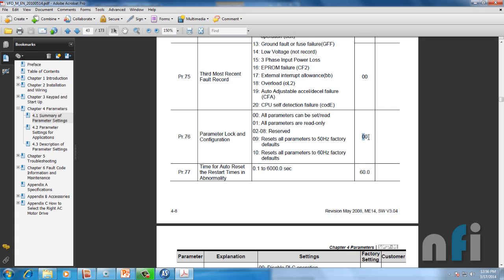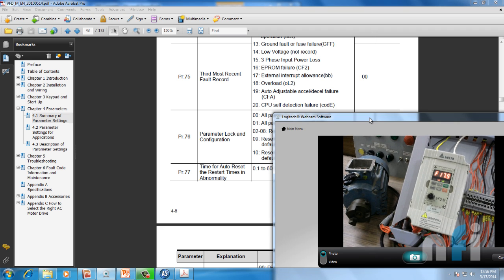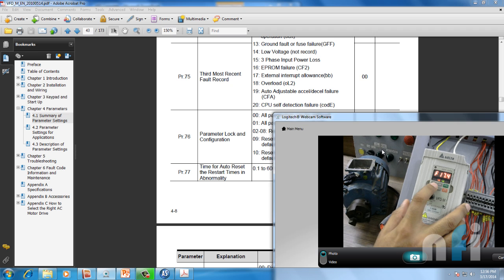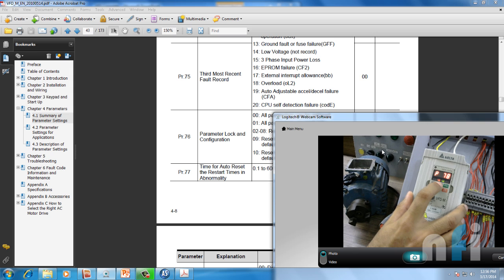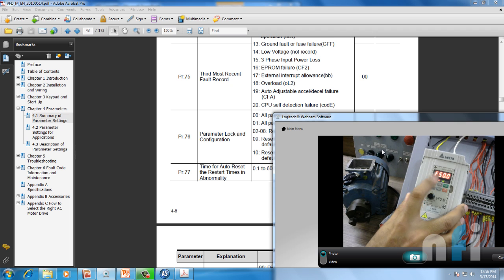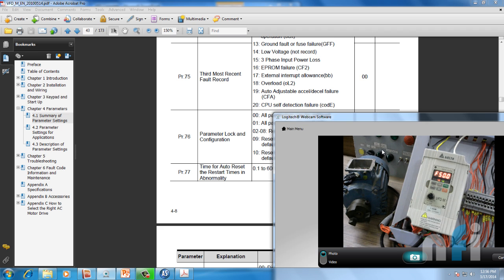In the manual, the reset parameters come at parameter number 76. If you put '00' in that, all parameters can be set — that's the default. If you put '09', it resets all parameters to 50 Hz factory defaults. So we have to enter 09 in parameter 76 to reset all parameters to factory settings. I'm going to parameter 76 by pressing mode once, incrementing to 76, pressing enter, then entering 9 and pressing enter. Now the default parameters are set.